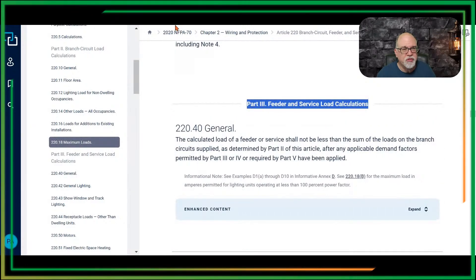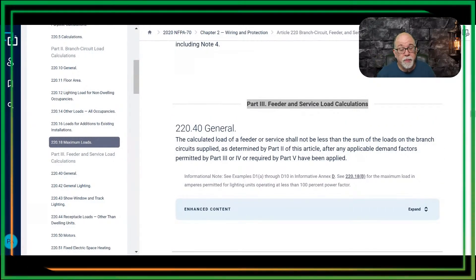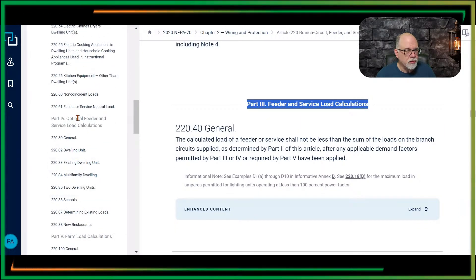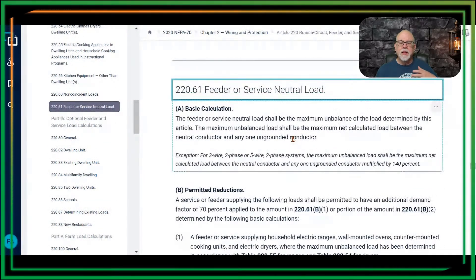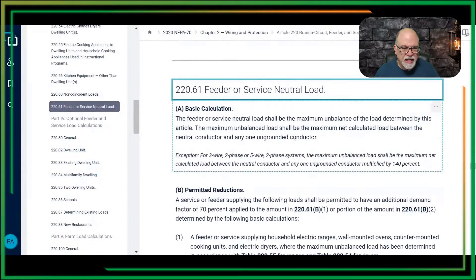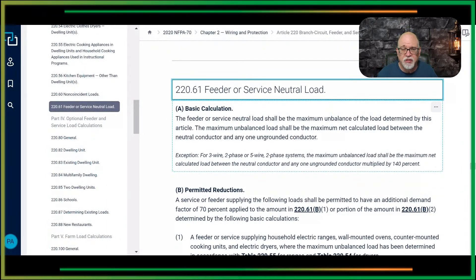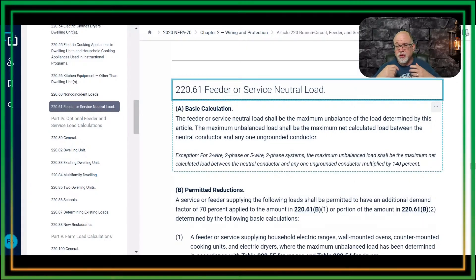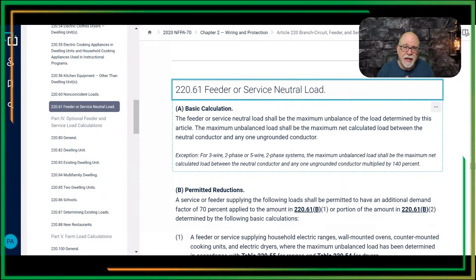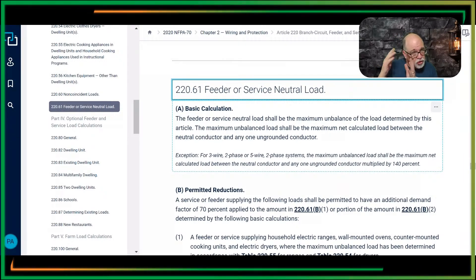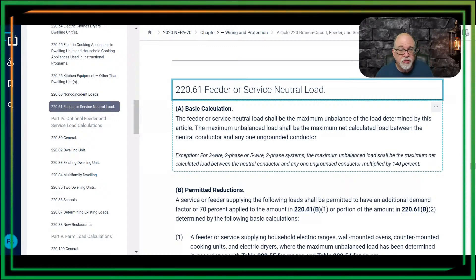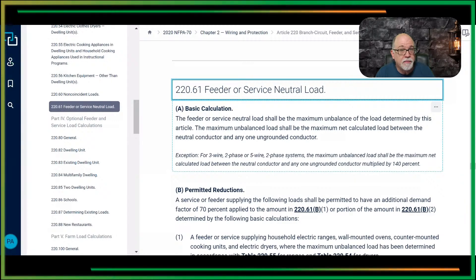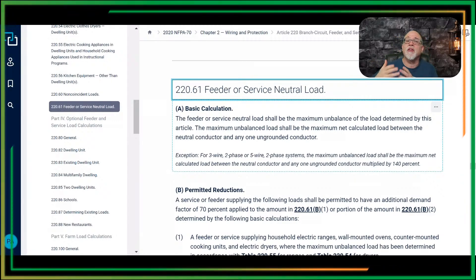Let's get back down so we can look at this neutral calculation. The concept hasn't changed — this is a permitted reduction. Say you do the load calculation for everything, and now you've got your neutral contribution. Your three VA per square foot is going to be counted because that's 120-volt loads — that's a neutral load. Your small appliance branch circuits — absolutely, there's a neutral load associated. Your laundry circuit — there's obviously a neutral. So all of those have a neutral contribution.